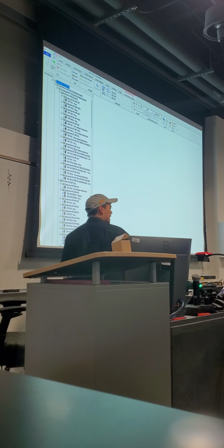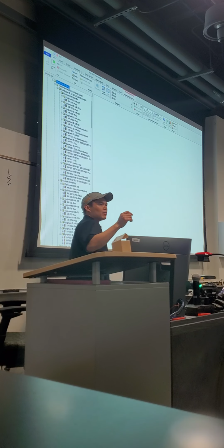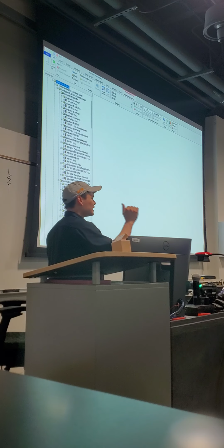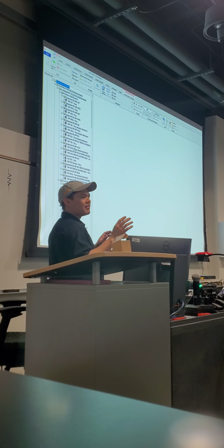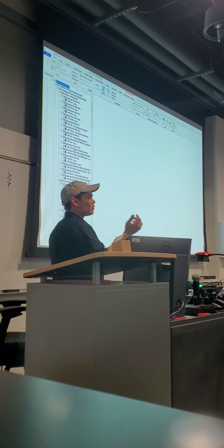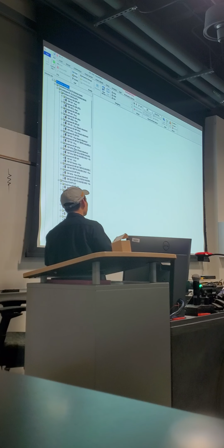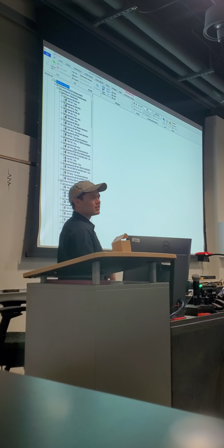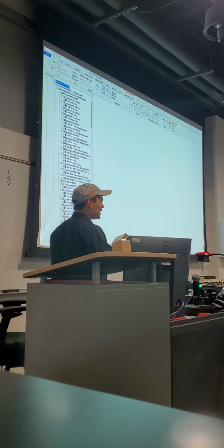You're seeing that the PI has a very good application, and we worked with Chevron to say this is what we'll have. If it's 1.5 PI, we're good, right? If it's below that, we're sending it out. Especially since this thing got caught up in the fires, they were sending out motors left and right to get rewound and refurbished, because who knows, are you really going to stake that a motor that was in a fire is going to perform? So they were erring on the side of caution. Normally you'll say anything above 1 is good for the most part for aged equipment, but they set certain thresholds to say, other than that, we're going to send them out. But these are all the motors we tested.